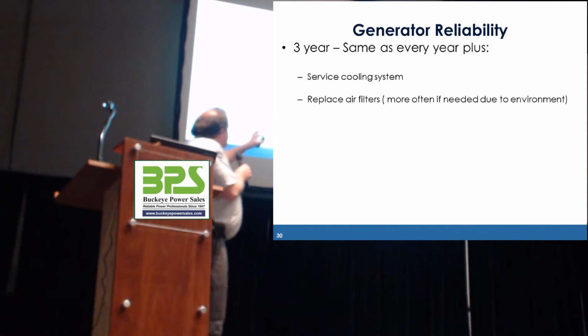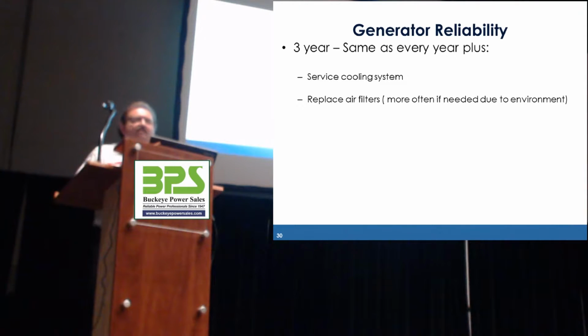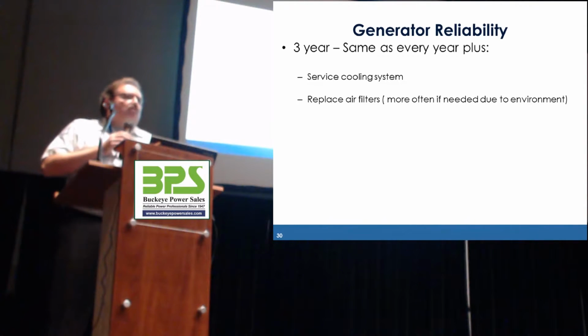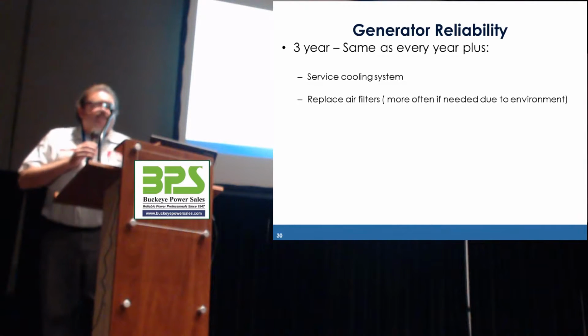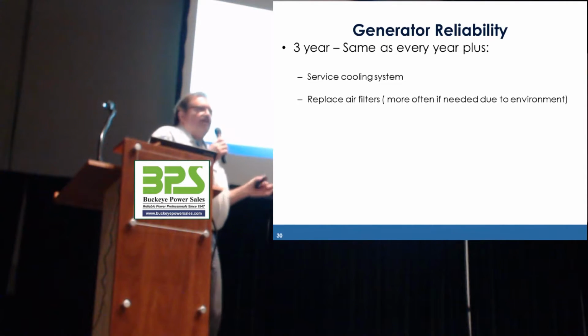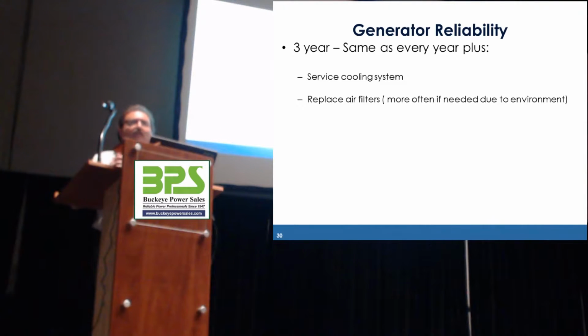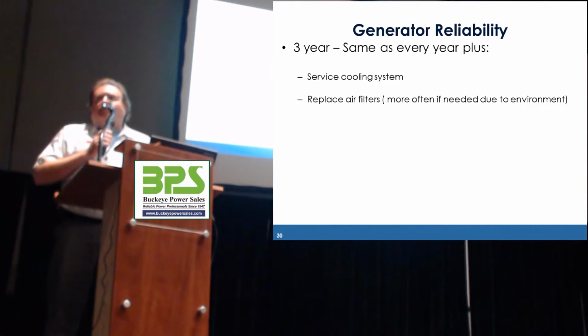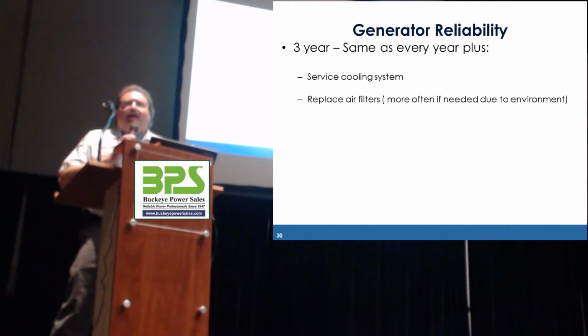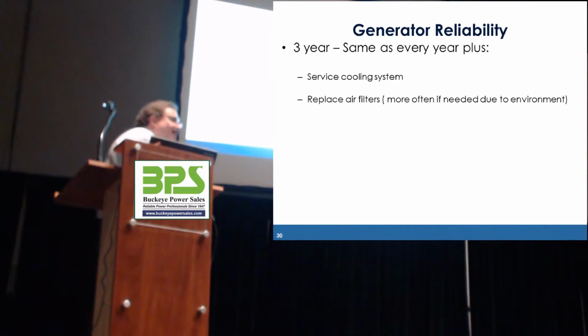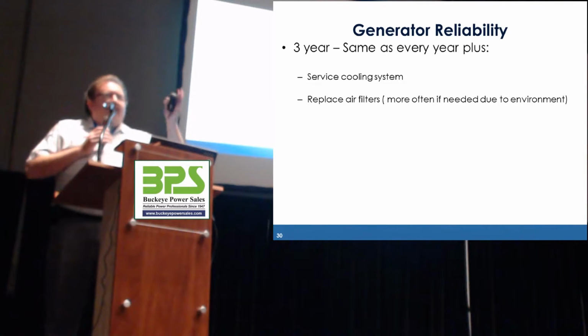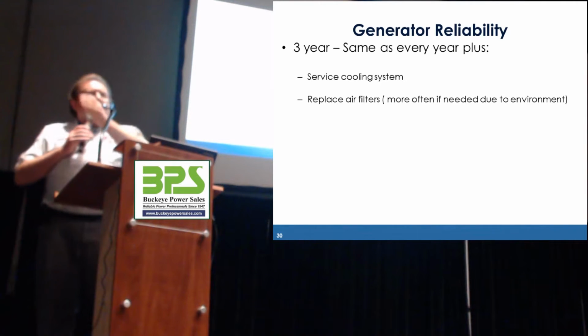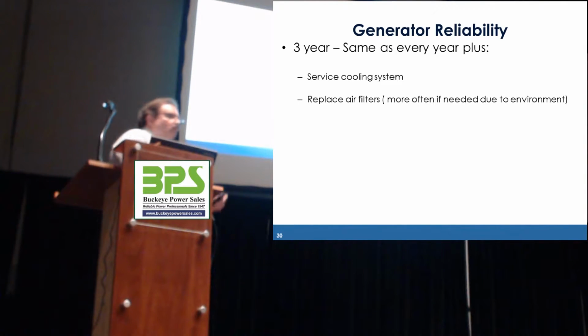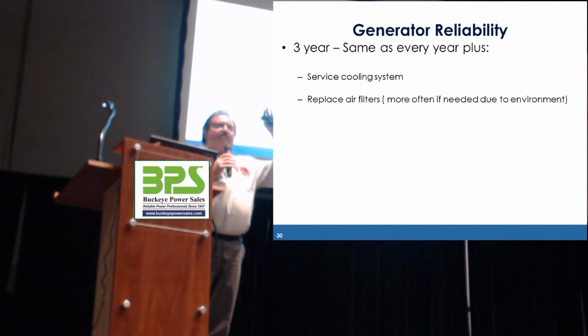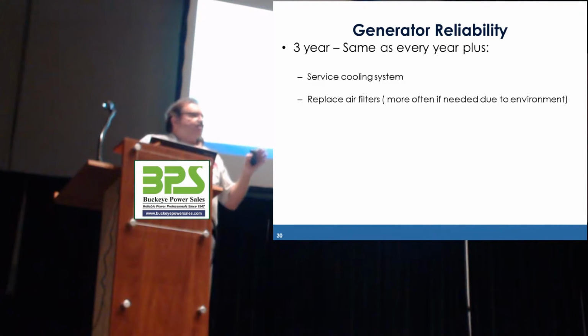Then every 3 years, we should be servicing the cooling system, right? Belts, hoses, thermostats, coolant, radiator caps, making sure radiators are pressure cleaned out, air filters being replaced. If it's a dirty environment, it may need more than that. Okay? Again, by the manufacturer's recommendation, this may seem like a little bit of overkill, but if you get into the habit of every 3 years, you do this maintenance in addition to your normal maintenance, then what are we doing? We're just trying to mitigate that potential issue.